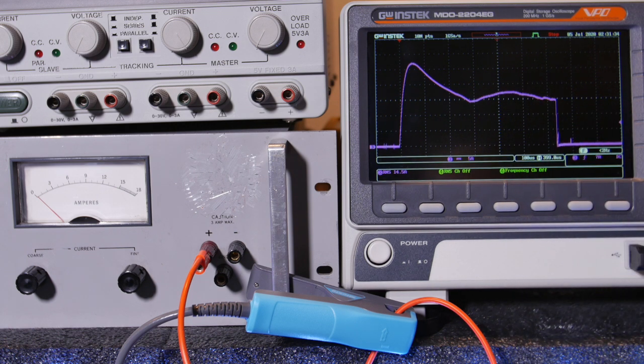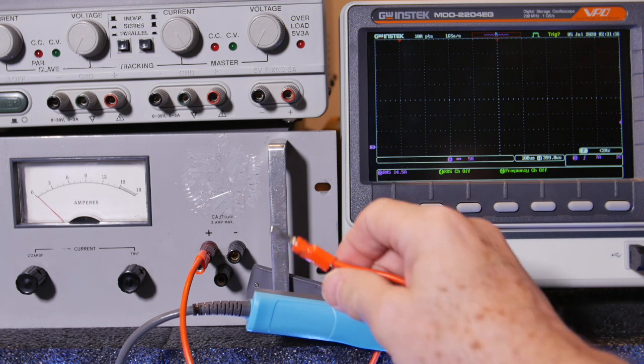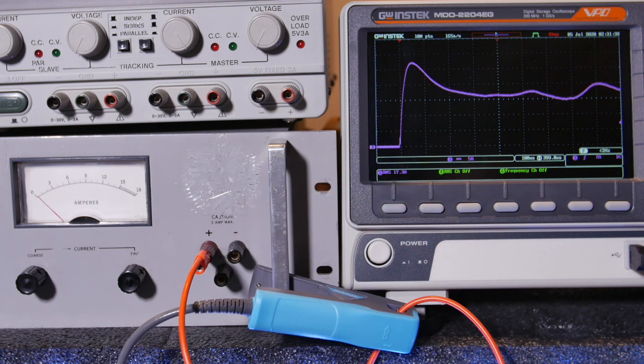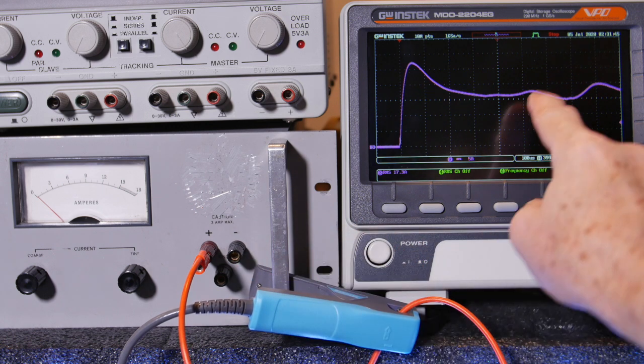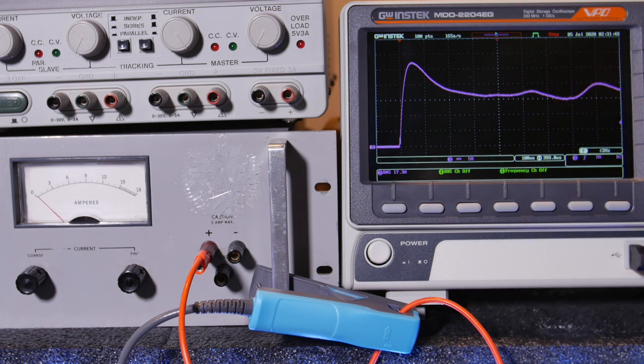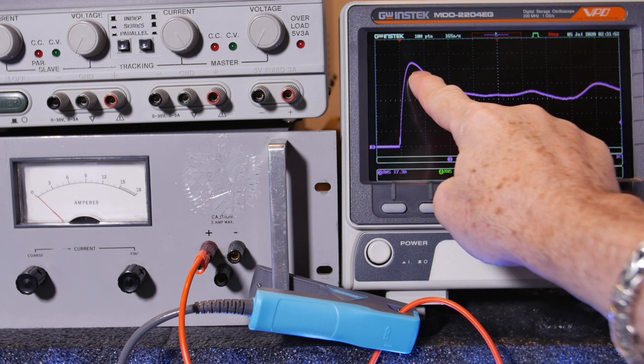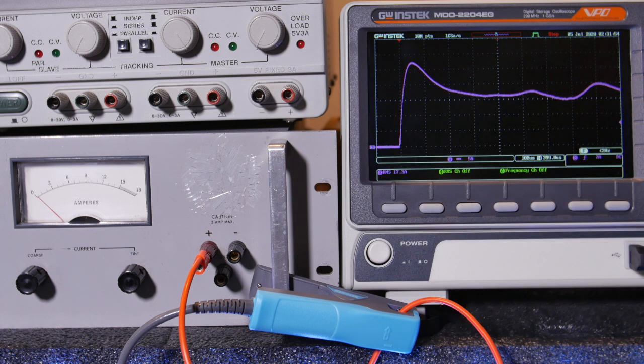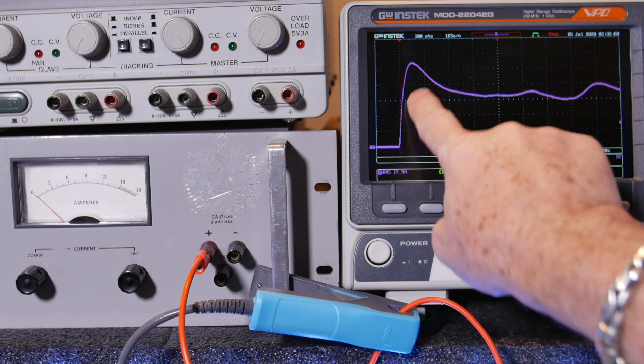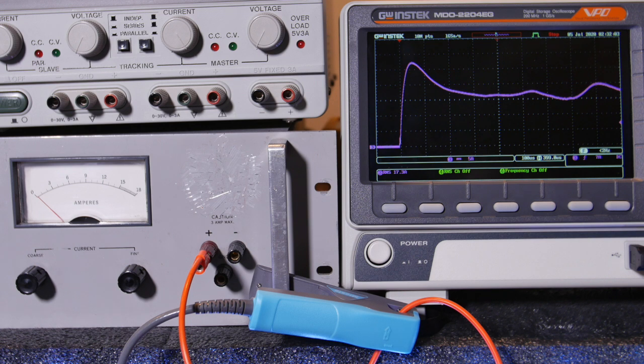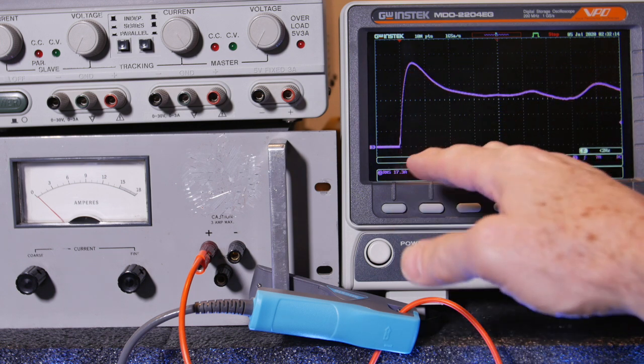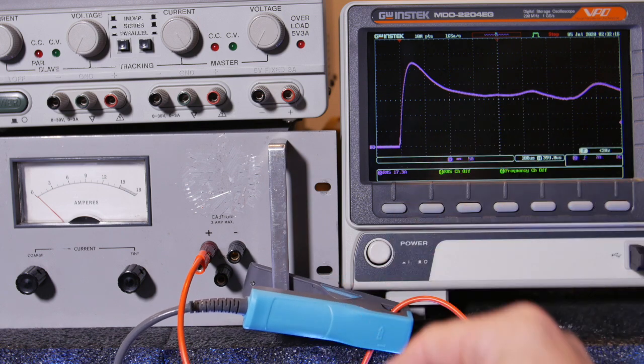So let's go ahead and single trigger and try that again. Here we go. Yeah, wow, look at that. Now, I'm probably bumping around on here, so that's probably why we're getting this stuff. But yeah, there we go. 5, 10, 15, 20, 25, looks like 28 amps maybe. And this is 100 microseconds per division, and that happened in less than half a division. So again, about 40 microseconds probably. So there's an inrush current. That's pretty cool. That's nowhere near as fast as this probe is capable of doing, but that was pretty cool.